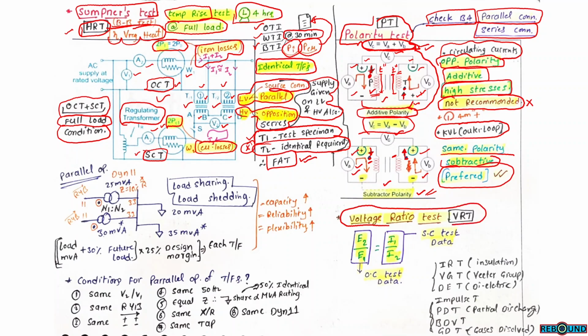Voltage ratio test. From the open circuit test, we can get this data, E2 by E1. From the short circuit test, we can get this data, I1 by I2. The data obtained from these two tests gives us the voltage ratio. These are other tests which we can perform on transformers.